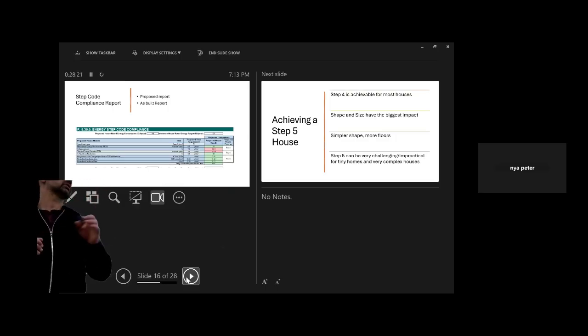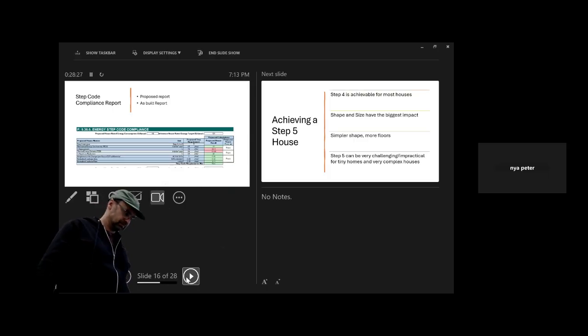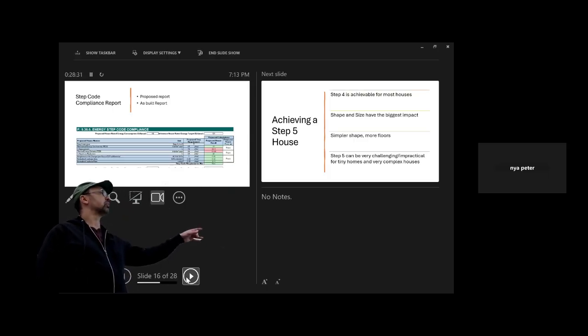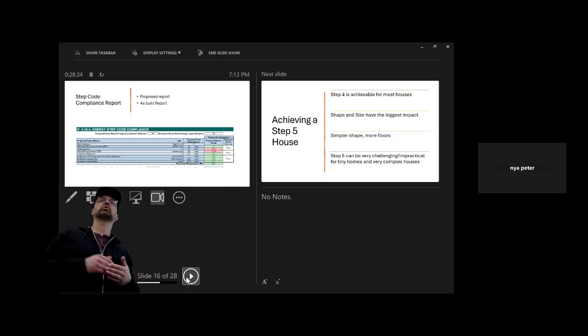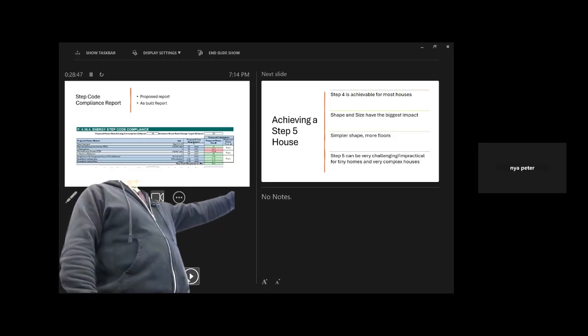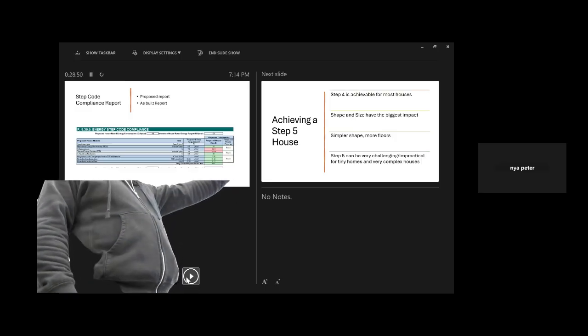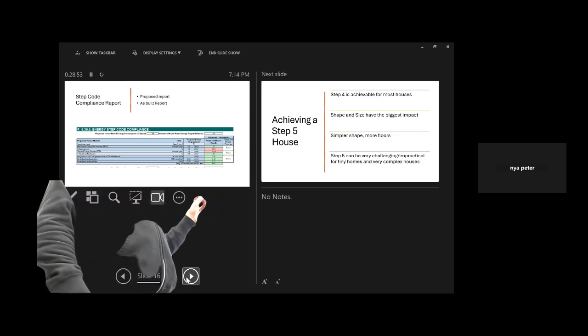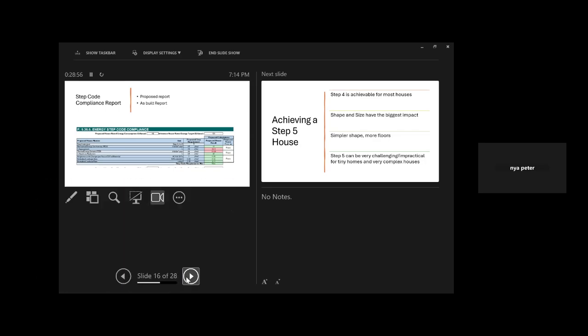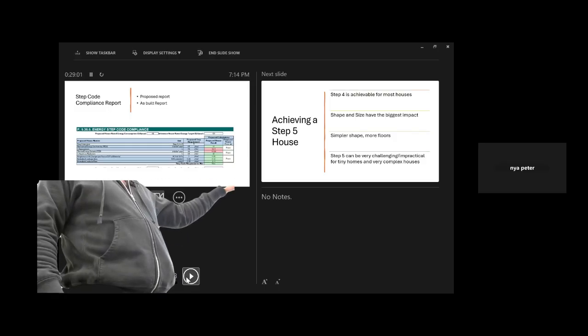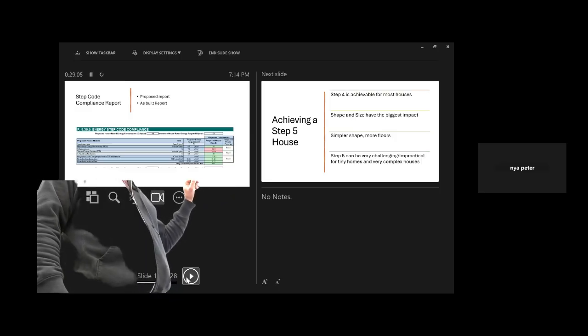I do it all up on Hot2000, and then I put it through this fancy Excel spreadsheet, and I come up with a report as to whether it hits step code 3 or step code 4. I usually show this is what you need to do to hit step code 4, and this is what you need to do to hit step code 5. So this one does hit the kilowatt hour per square meter, but it's not 70% better. For the thermal energy demand, it is 40% better for the TEDI, but it doesn't hit the kilowatt hour metric.